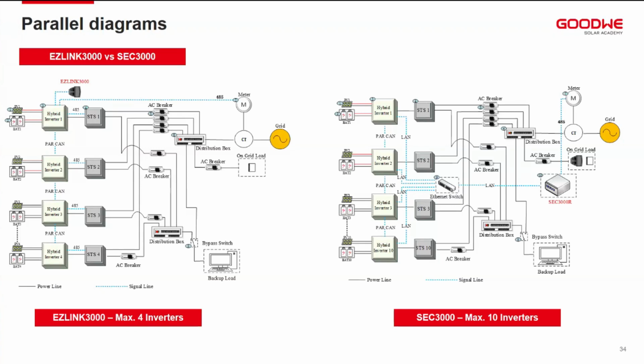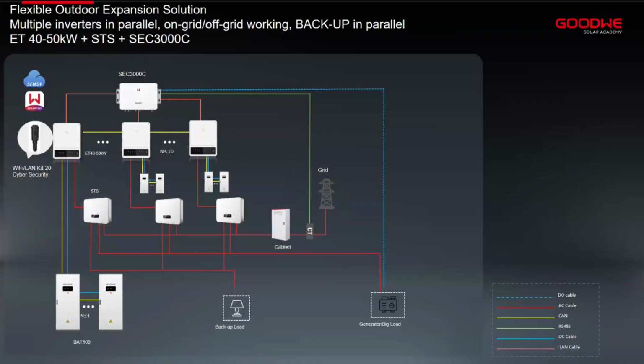Now, in this up to 10 inverters, you can see we're not really doing a master-slave. All the inverters are directly reporting to the controller itself. So through the LAN connection to the Ethernet switch or the router, all the inverters will be connecting to the SEC3000C. So if any inverter fails, the rest still continue as long as the remaining inverters can handle the loads. Using the STS, as you can see, the inverters can parallel or they can share loads for the on-grid ports, and they can also share loads that are on the backup port. So the whole system can be sized up or scaled up to become a mini grid, or even a microgrid. Now this scenario actually brings us to this.